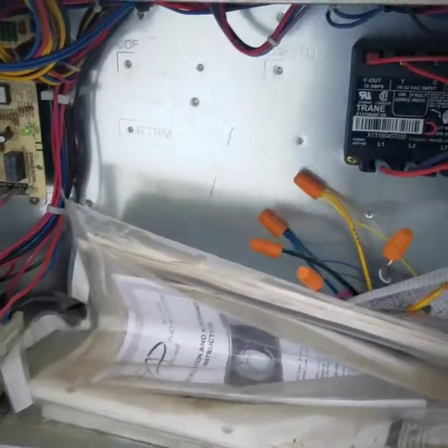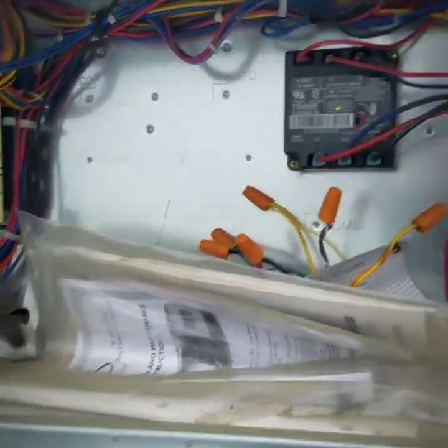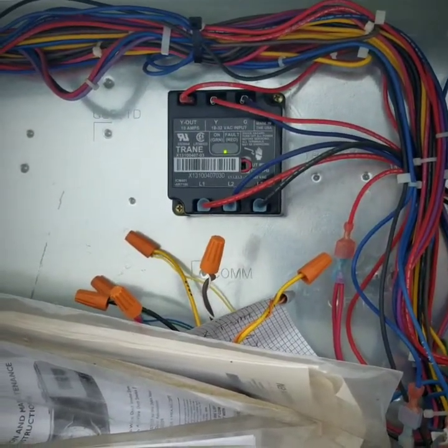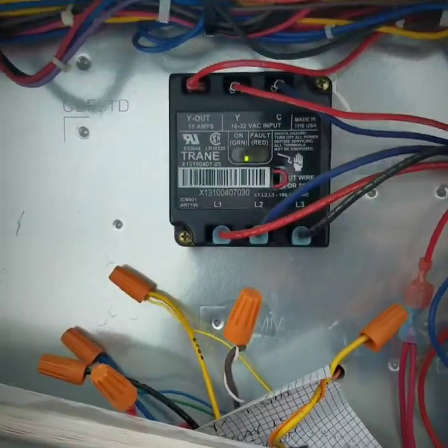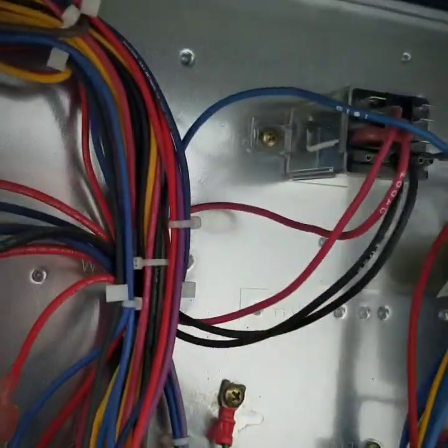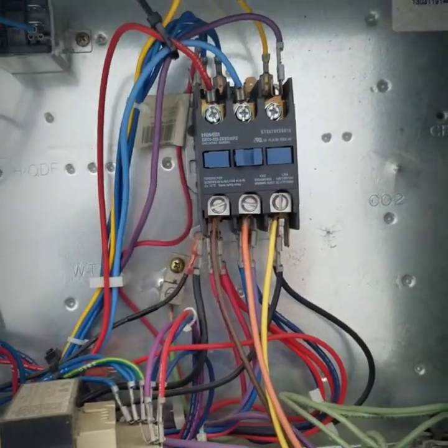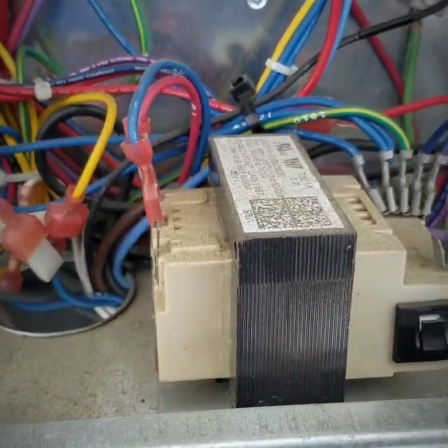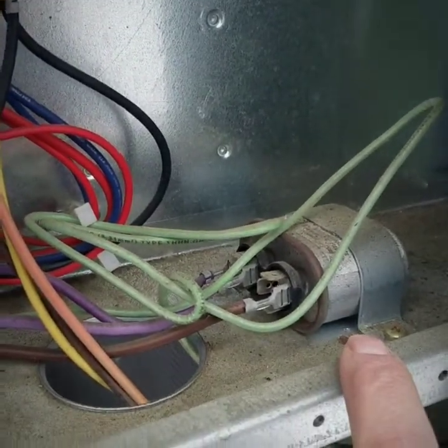Over here in the control area you have your ignition control board for the heat. The phase monitor right here is basically a safety for making sure the rotation is correct — it will show a green light if it's good and a red light if it's not. This is for fan control, it's just an ice cube relay. Right here we have a contactor for your compressor, a transformer to take your line voltage down to low voltage, and then a capacitor which is for your outdoor fan motor.